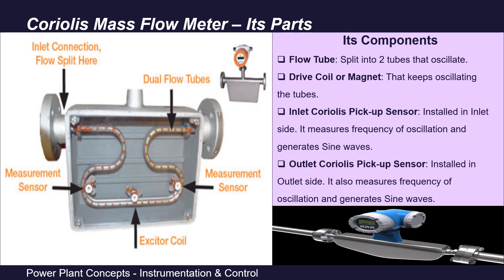The third important parts are the sensors. Two sensors — called Coriolis pickup sensors — are installed in the Coriolis flow meter. One sensor is at the inlet side and the other is on the outlet side of the tube — one upstream of the exciter coil and one downstream. These sensors measure the oscillating frequency and generate sine waves. Other parts include the casing and flange connections at the inlet and outlet side to install it in the process pipeline.